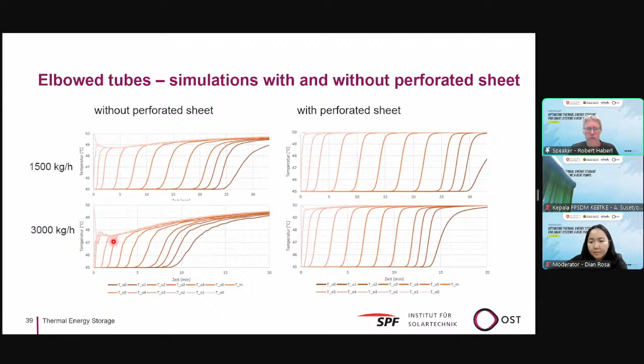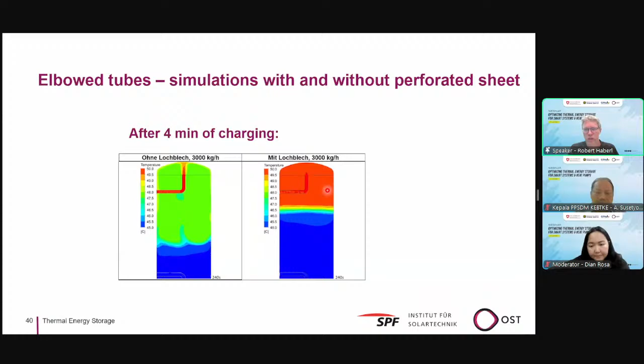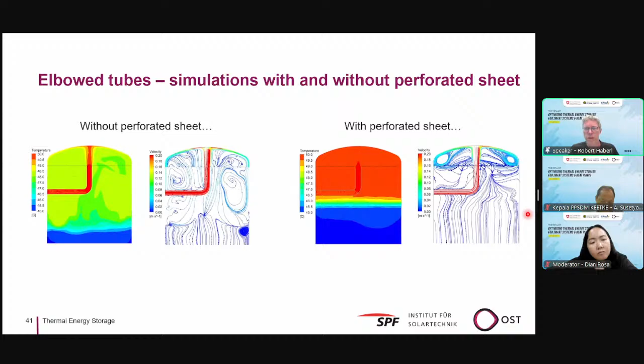You see here again CFD simulations with this case I showed before. Only after 4 minutes you have a very big region where you have mixing without a perforated sheet. And if you use a perforated sheet, you keep the hot water hot and the cold water cold, which is the goal. And here you see the streamlines of the fluid. You have the perforated sheet somewhere here, and the streamlines are very evenly distributed, having a piston flow in the whole storage tank, meaning you push the hot water down to the bottom of the tank without destroying the thermocline between hot and cold.